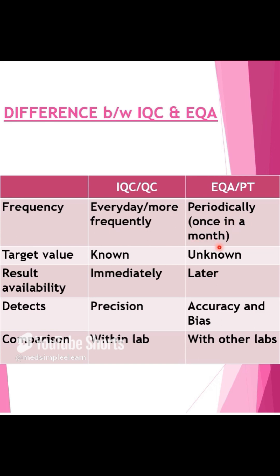The second important difference is target value. For IQC, the target value is already known when we are running the IQC sample. While in the case of an EQA sample, the value is not known to the user when the sample is being run — it is only available after the results are provided by the provider.